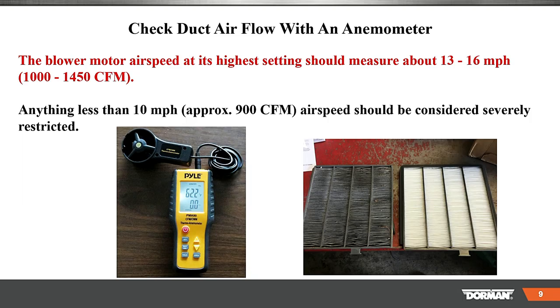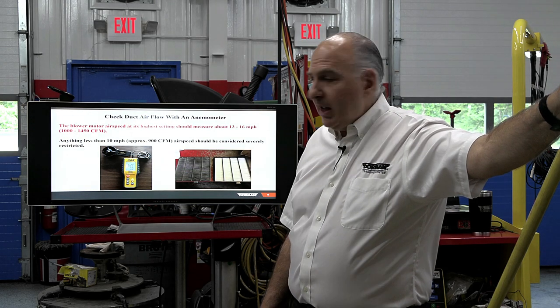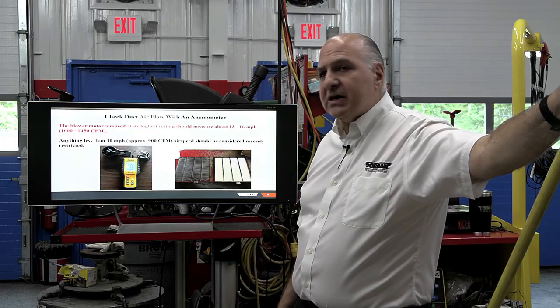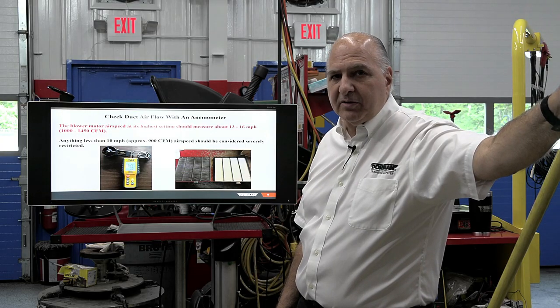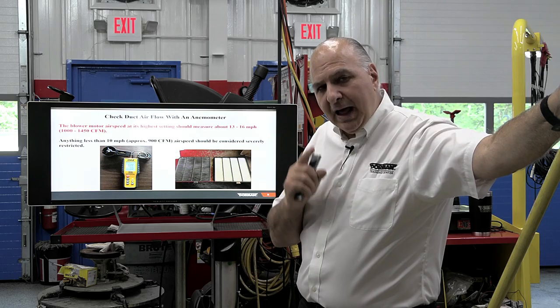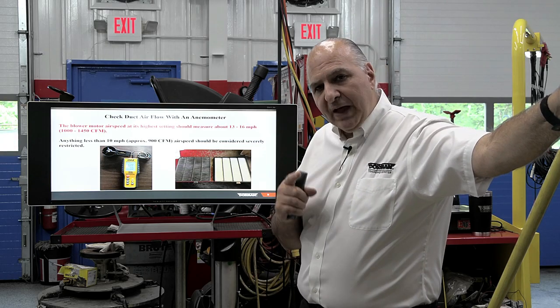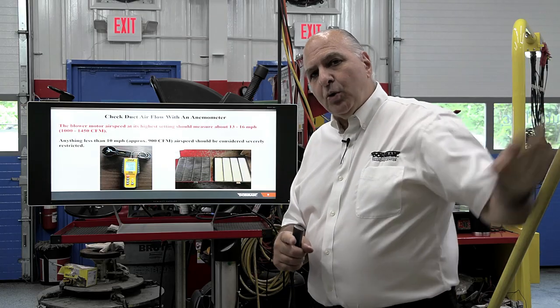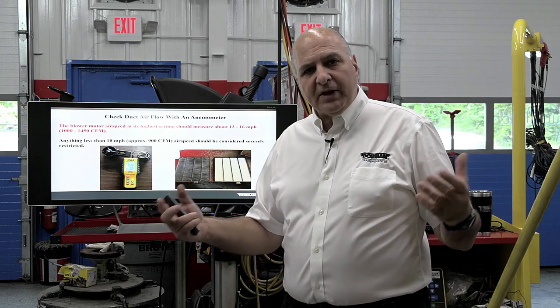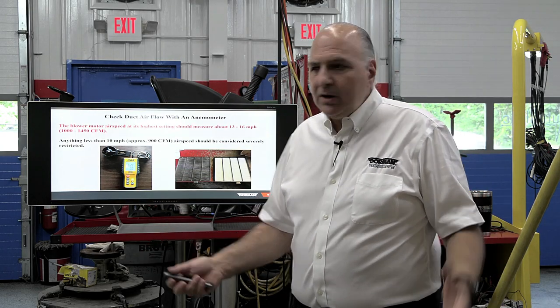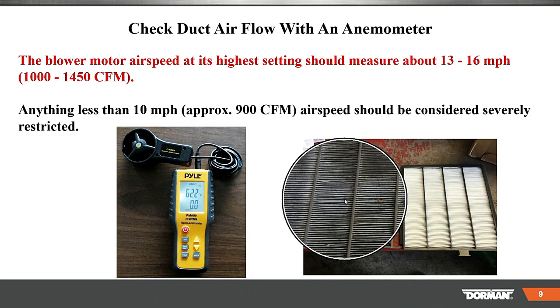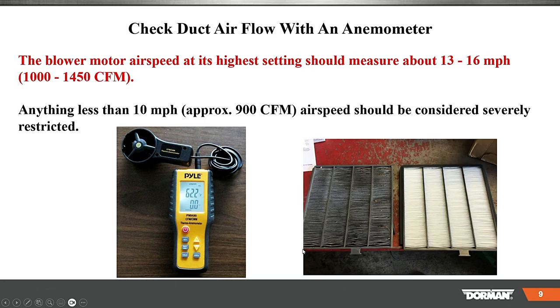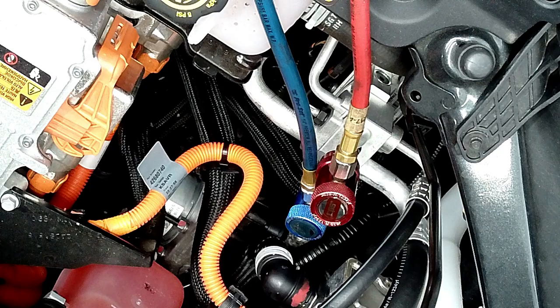You want 13 to 16 miles an hour, or 1,000 to 1,450 cubic feet per minute, okay? If anything is less than 10 miles an hour, approximately 900 standard cubic feet per minute, you are gonna have a problem. You will not have proper air distribution, which will then make the customer think they're not getting cool enough. Well, look at the difference of these filters, look at that dirty filter versus a clean one, and the difference in air that could flow through the system.